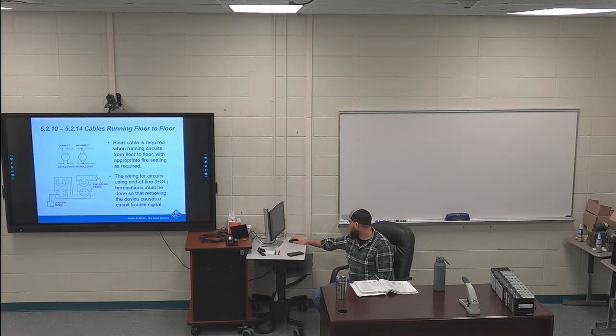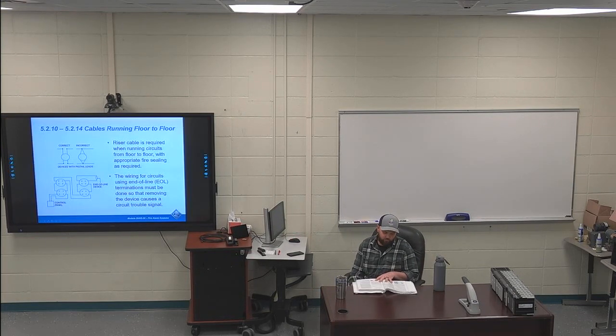Wiring in the air handling spaces, nothing highlighted in that section in 5.2.7, 8, or 9, but we will be talking about sensing in air handling spaces. PowerPoint back up. So my next highlight is in 5.2.10, cables running floor to floor. First sentence of 5.2.10 is highlighted. Riser cable is required when wiring runs from floor to floor. So it's a special rated cable called riser cable.